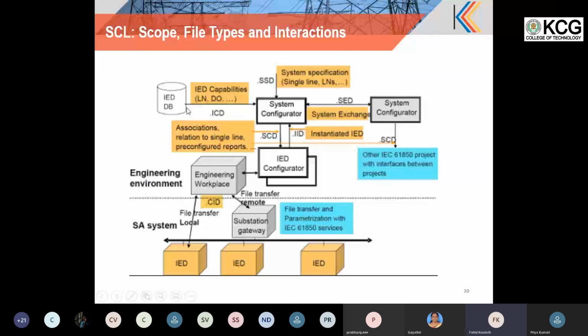Using that, you will have a link of the substation elements to the actual data. That is, from this IED this breaker data is coming, and this breaker command can be given through this IED. Like that, you can have a link between the substation SLD and the real data coming from the IEDs. Once this is done completely, it is known as a superset file for a substation, including all the substation specification and real data coming through the IEDs, and that file is known as the substation configuration description, the SCD file.